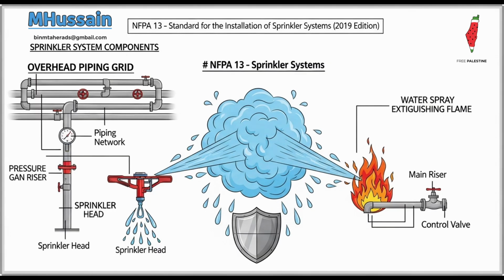Now, for advanced systems like control mode specific application, CMSA, and early suppression fast response, ESFR sprinklers, the standard mandates a significantly higher minimum nominal K factor. We're talking K11.2, which is 160 in metric. And how does that scaling work when you get into those really massive K factors? Well, the K factor isn't linear in its impact. Once you move past the standard K5.6, or 80 heads, sprinklers with K factors greater than K28, that's 400 metric, essentially double the flow in 100% increments compared to that standard K5.6.